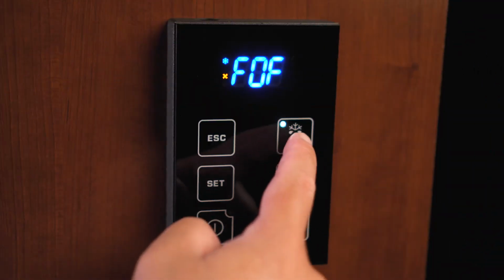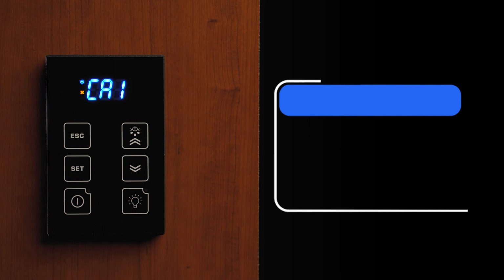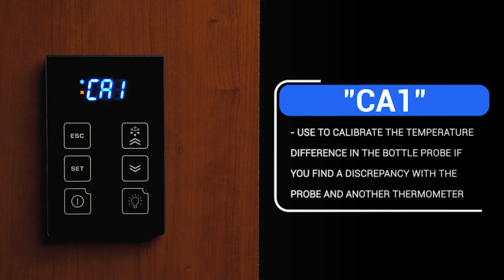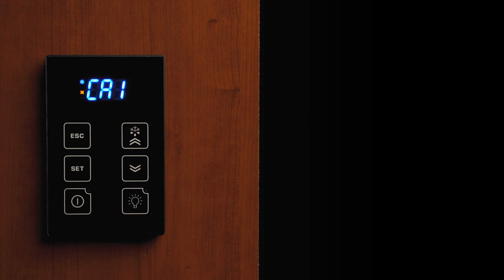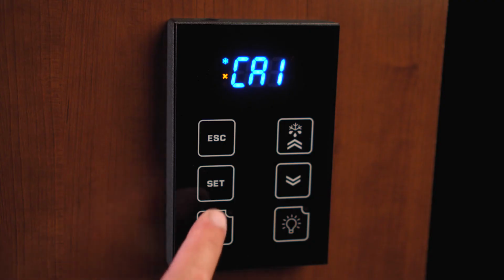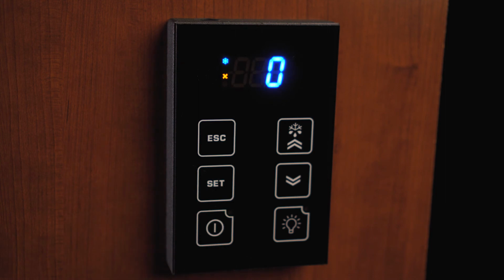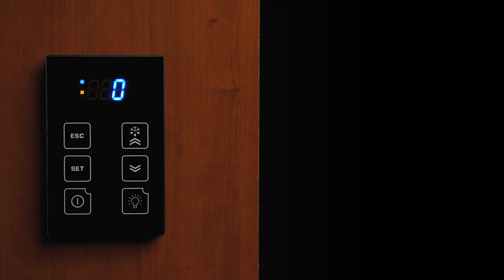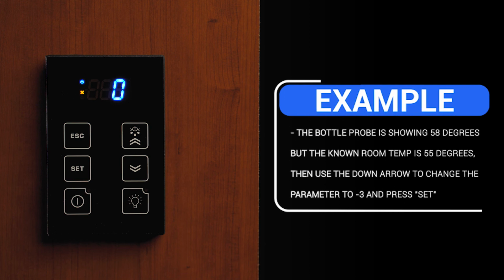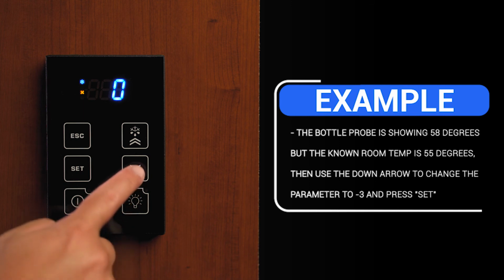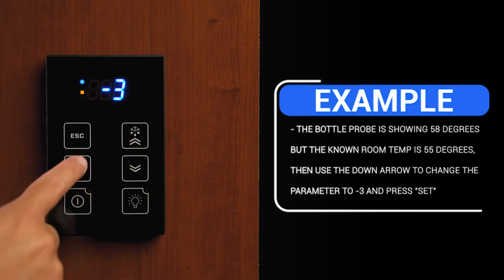CA1 is for the bottle probe calibration. You may use this parameter to calibrate the temperature difference in the probe if you discover there is a discrepancy in the probe temperature with another thermometer. To access this folder with CA1 on the display, press the Set button and release it. The factory setting should be 0. For example, if the bottle probe temperature is displaying 58 degrees, but the known temperature is 55 degrees, then you would use the down arrow to -3 to match the known temperature.